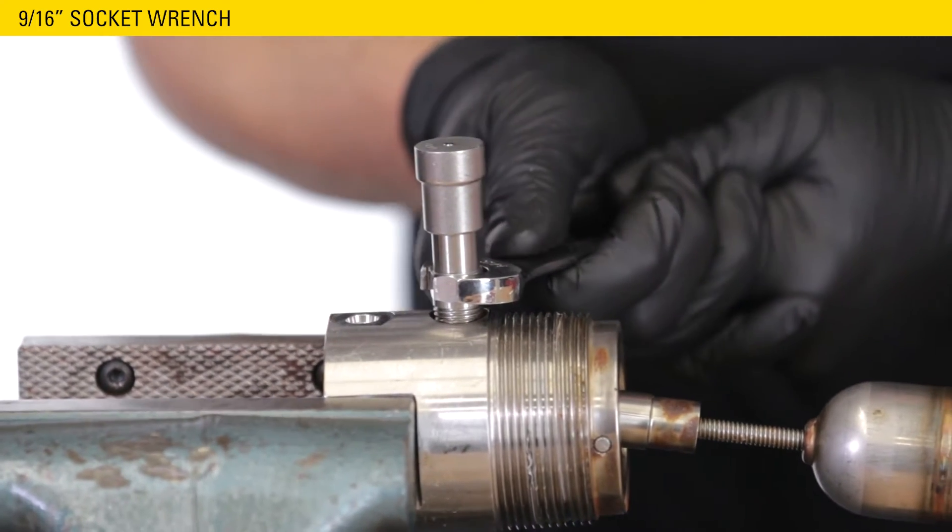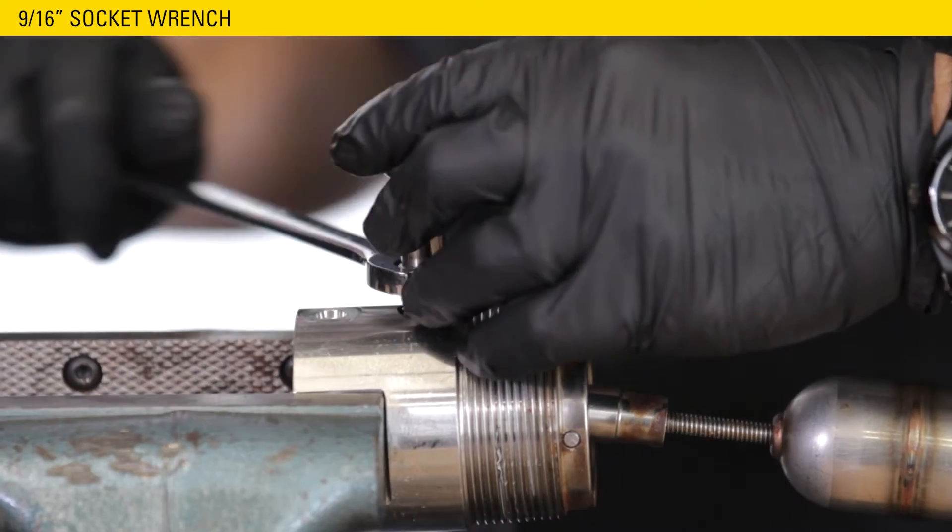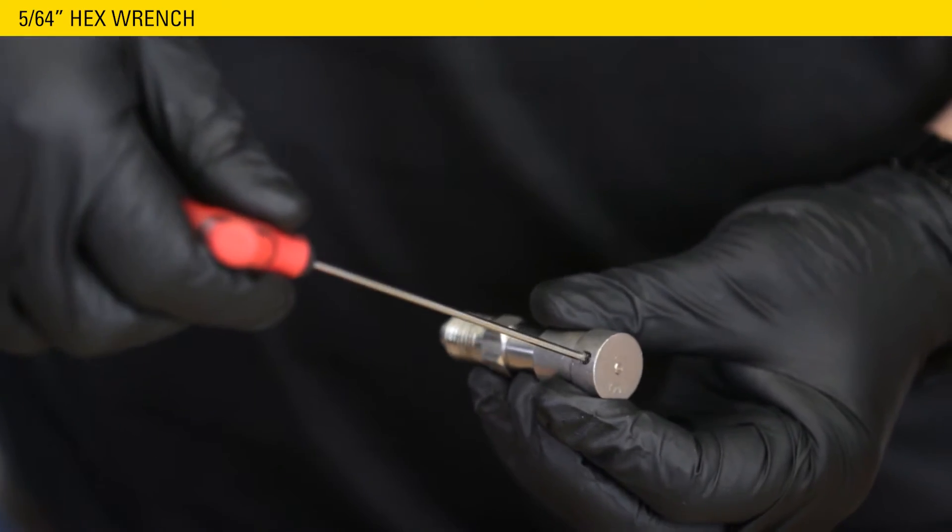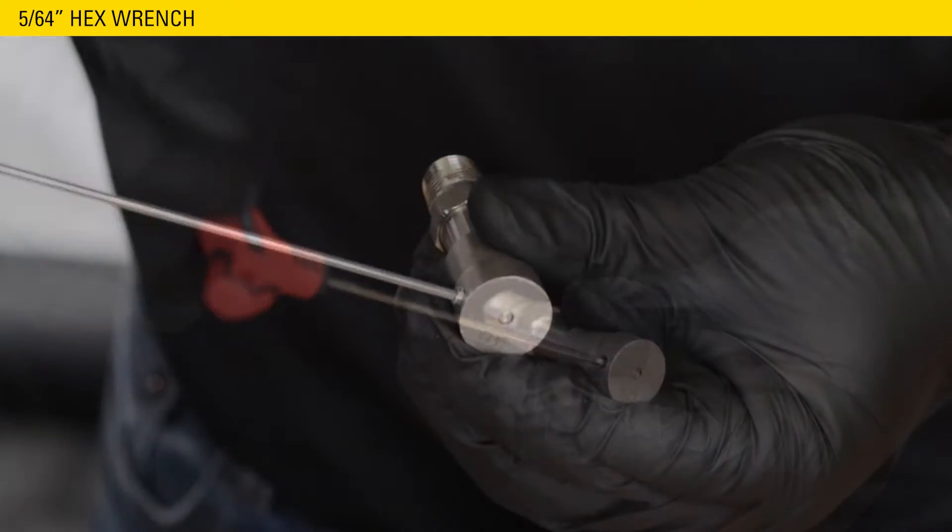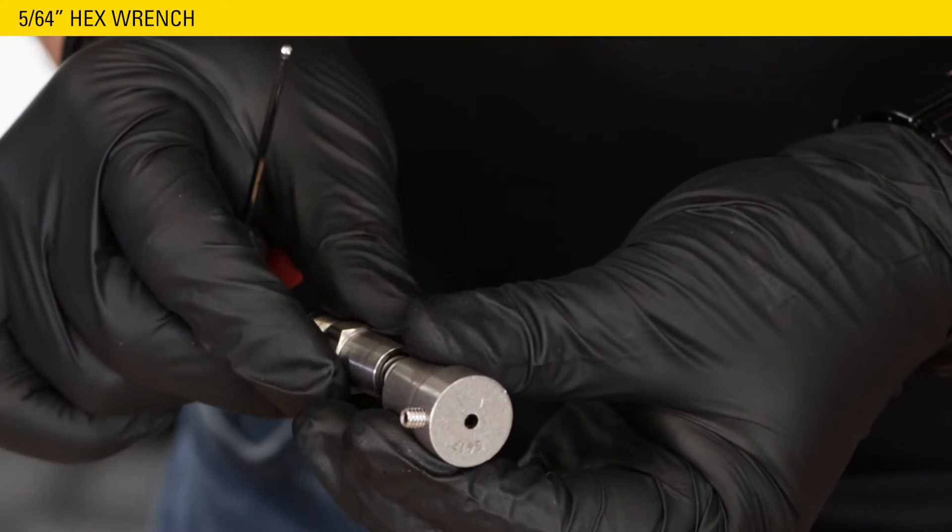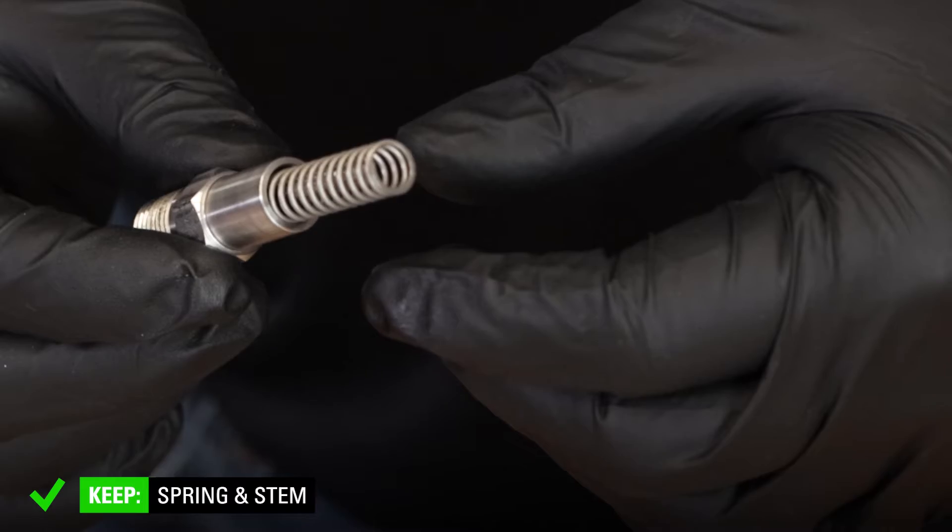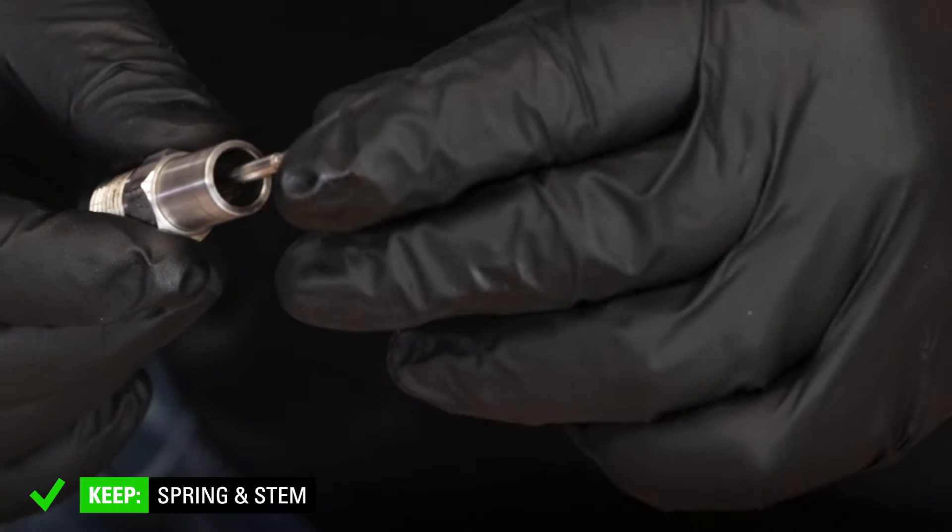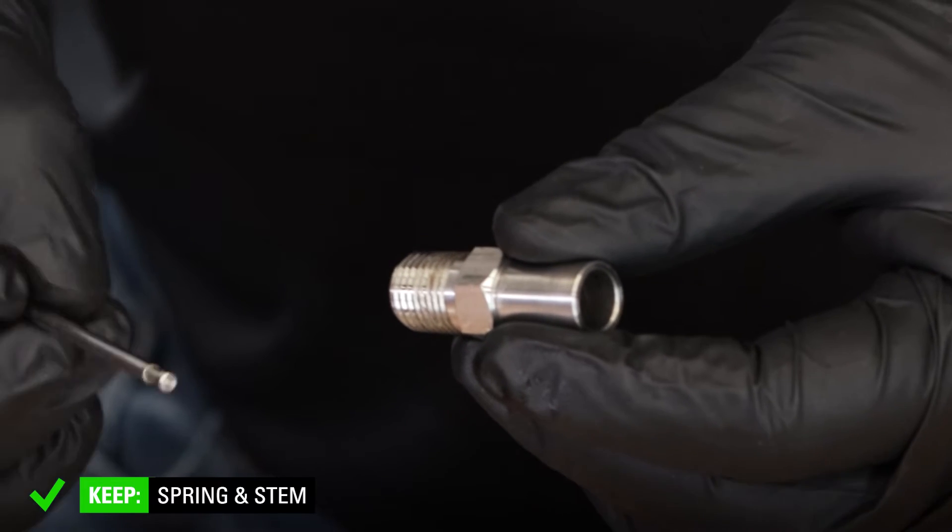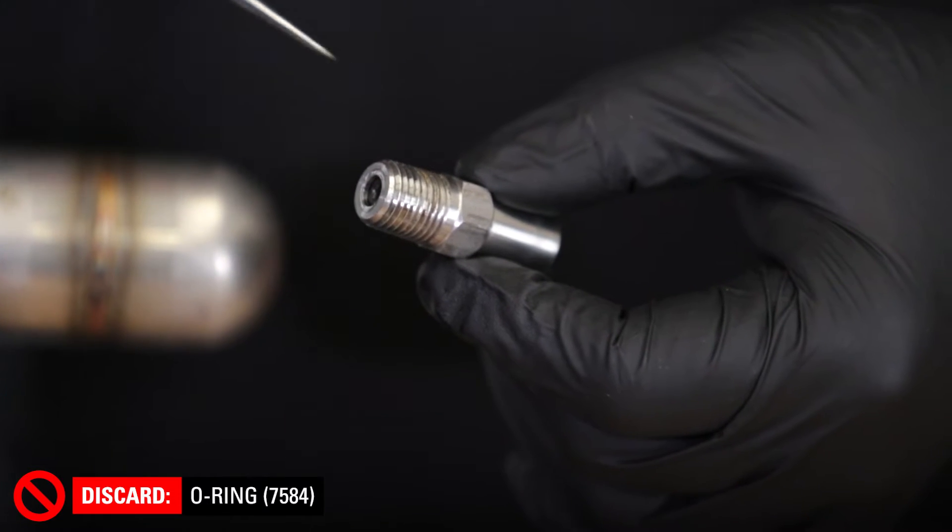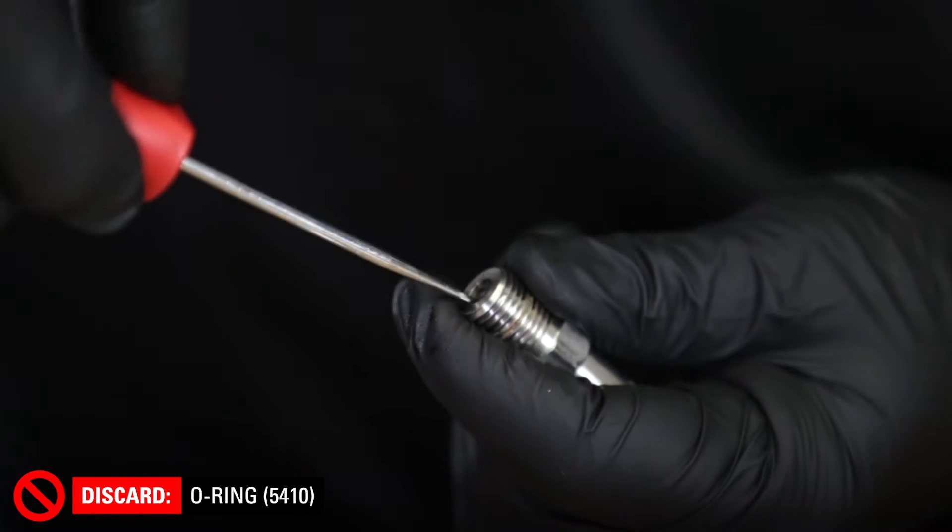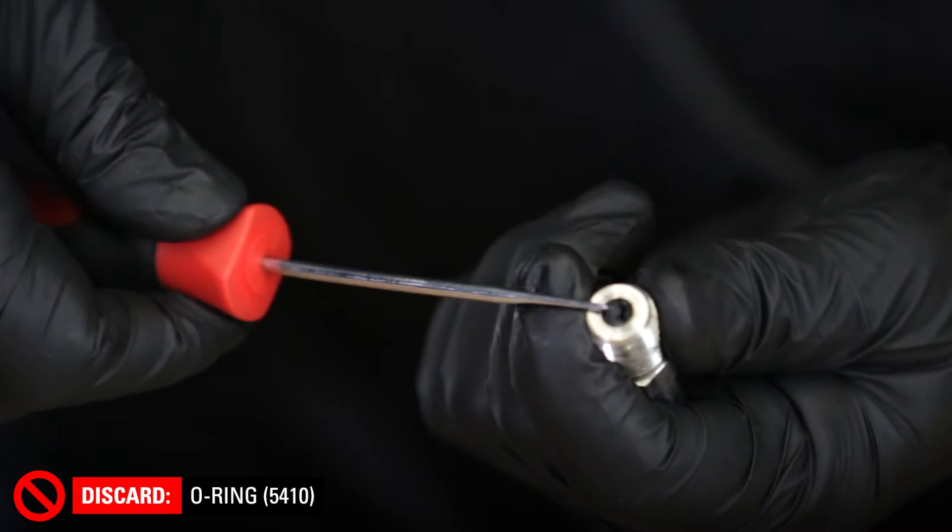Next, we'll disassemble the override fitting. Use a 9-16 wrench to loosen the override fitting. Use a 5-64 hex wrench to unthread the set screw and remove the cap. Now remove the spring and stem and set them aside. Remove and discard the O-ring from the threads on the override. On our level switch, the O-ring had disintegrated so there was nothing to remove. And lastly, use a straight pick to discard the O-ring located inside the override.